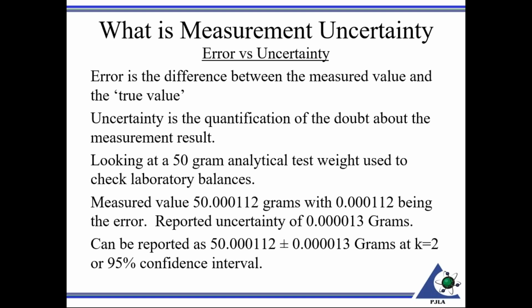Let's look at another term here, error versus uncertainty. An error is the difference between the actual measured value and the true value. And the uncertainty is the quantification of the doubt about the measurement itself. So for example, we'll take a look at a 50-gram analytical test weight. Its nominal value is 50 grams. And you use this analytical weight perhaps to check the analytical balances in your laboratory.